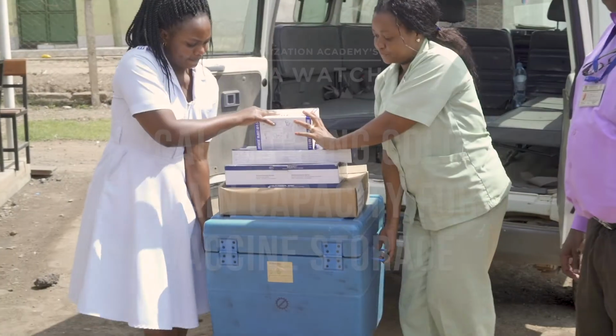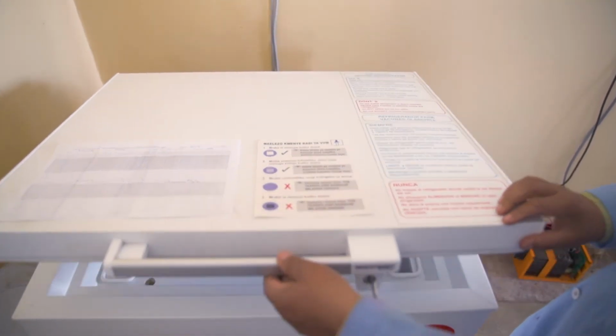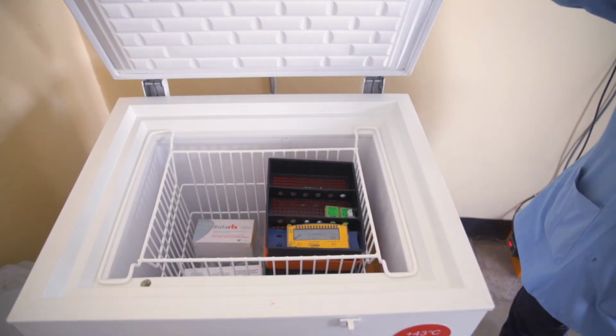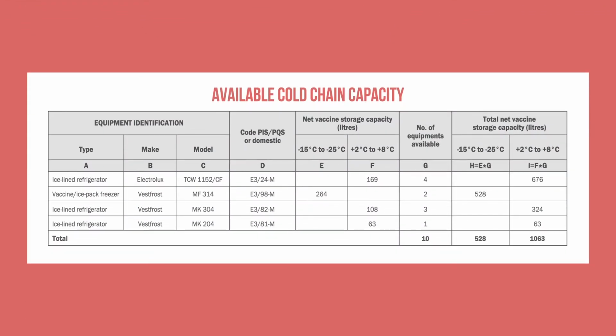To calculate your cold chain storage capacity, you will calculate the capacity of each type of available cold chain equipment and then add those estimates together. Let us use this table to walk through the calculation. List the types of cold chain equipment you have, including equipment specifications.